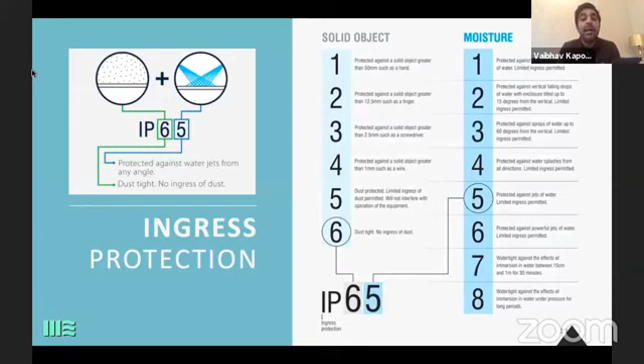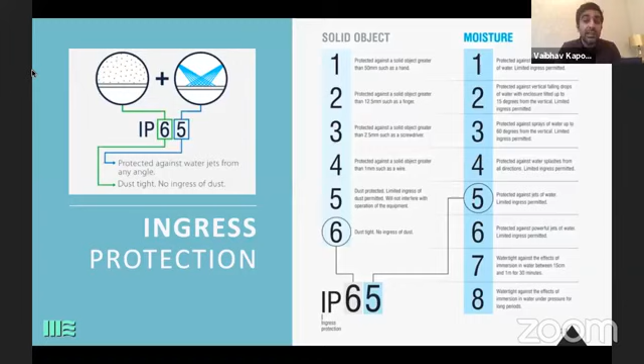So if your panel is kept outside and it starts drizzling, it starts raining, it can be water resistant, it can't be waterproof. There are certain things which have to be waterproof. Comes the IP67 rating, which says watertight against the effects of immersion in water between 15 centimeters and 1 meter for 30 minutes. Certain equipment comes in IP65, certain equipment comes in IP67. So simple: dust, rodents and water. That is your IP ratings; any power distribution electrical equipment has to be IP rated.